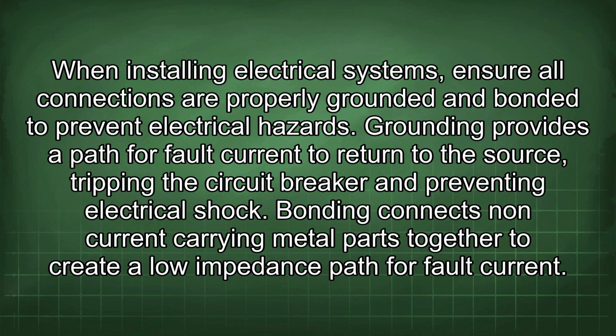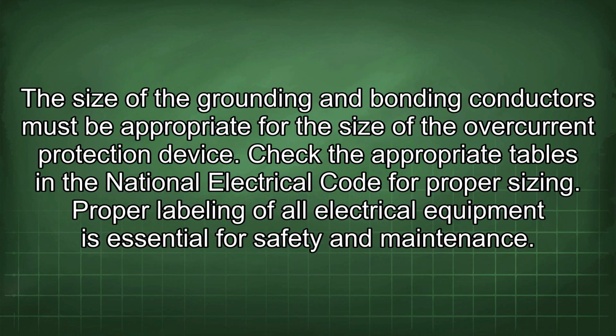When installing electrical systems, ensure all connections are properly grounded and bonded to prevent electrical hazards. Grounding provides a path for fault current to return to the source, tripping the circuit breaker and preventing electrical shock. Bonding connects non-current carrying metal parts together to create a low impedance path for fault current. The size of the grounding and bonding conductors must be appropriate for the size of the overcurrent protection device. Check the appropriate tables in the National Electrical Code for proper sizing.